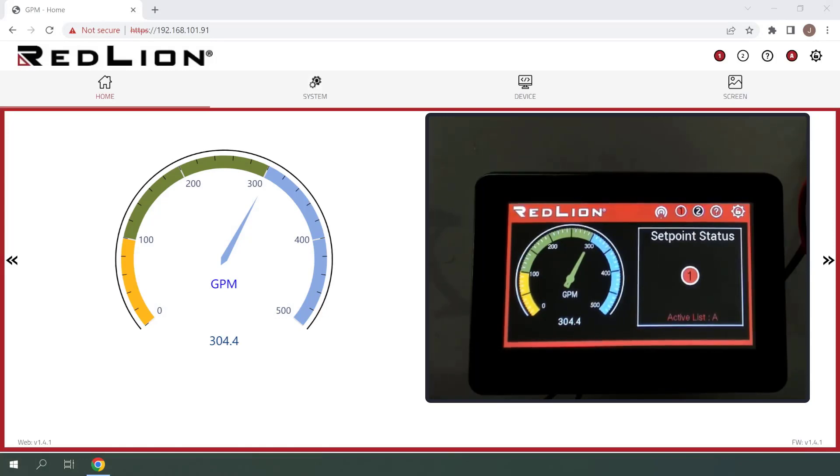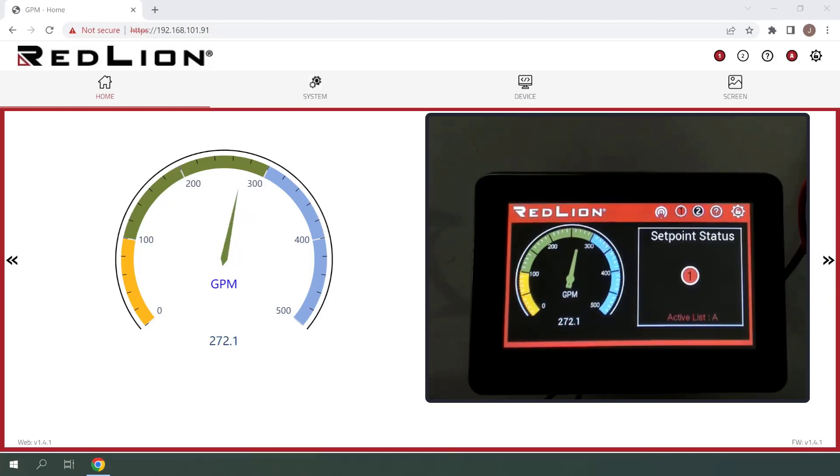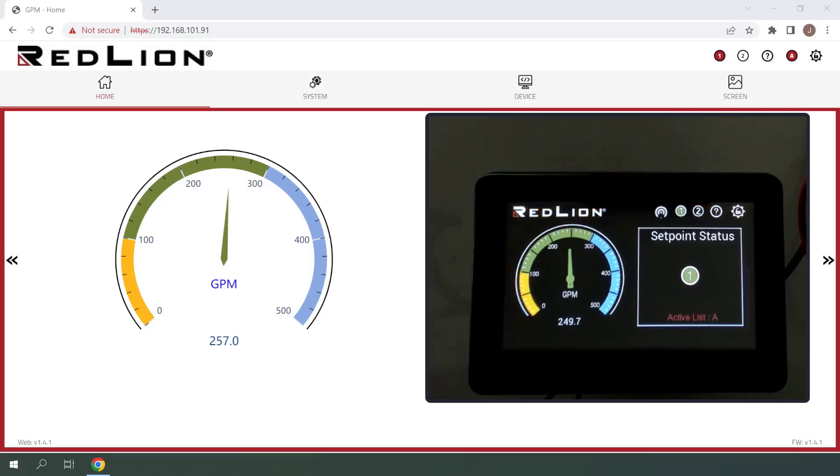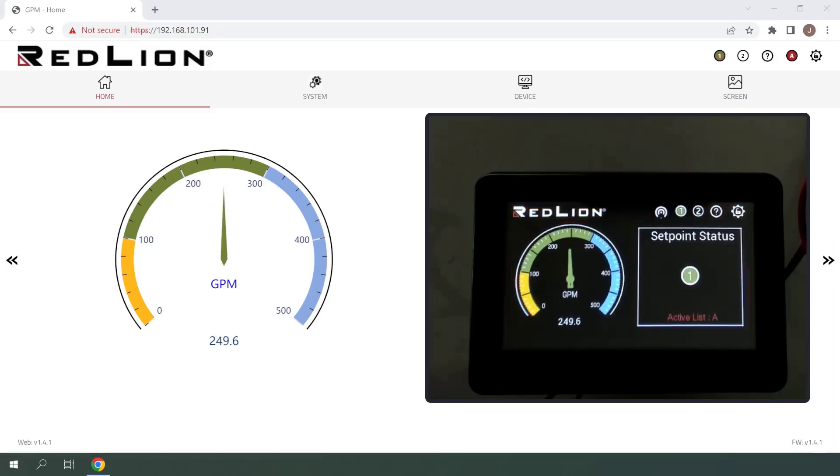I will now start to decrease the flow. You can see that the alarm is staying active as expected even though we're below 300 GPM. This is due to our hysteresis value of 50. And now that we are lower than 250 GPM, which is our setpoint minus hysteresis, we can see that the alarm automatically reset as expected.